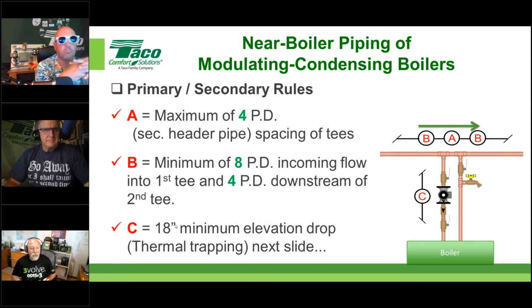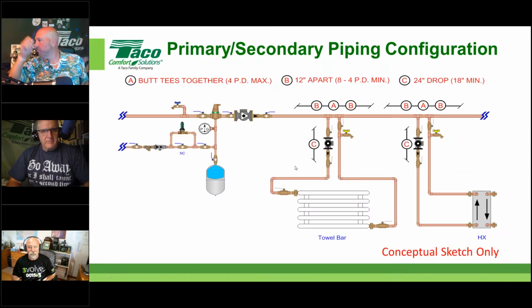And we're not going to talk too much about the C note. The C note in our case is just thermal trapping, and it's normally associated with variable speed injection mixing. It was always part of that third thing that people had to get their head around when they were doing variable speed injection mixing. But generally speaking, it's a thermal trapping. It's saying that the hotter water will never naturally migrate down very far, and that's why we give you a distance there as well.